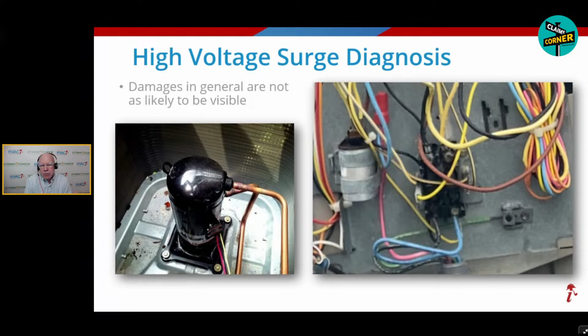All right. So, what you're looking at here is a compressor being tested. They got their ohmmeter out, they got it attached to it. They have the red wire on the positive of the terminal going to the compressor, and then they have it grounded. They have it set the proper way. They're getting this reading on their screen which is telling the technician a current is being allowed to go from the motor to ground. And if you haven't heard that term before, it's called shorted to ground, which is basically short circuited or shorted out, right? You've heard those terms, right? That is not supposed to be happening.